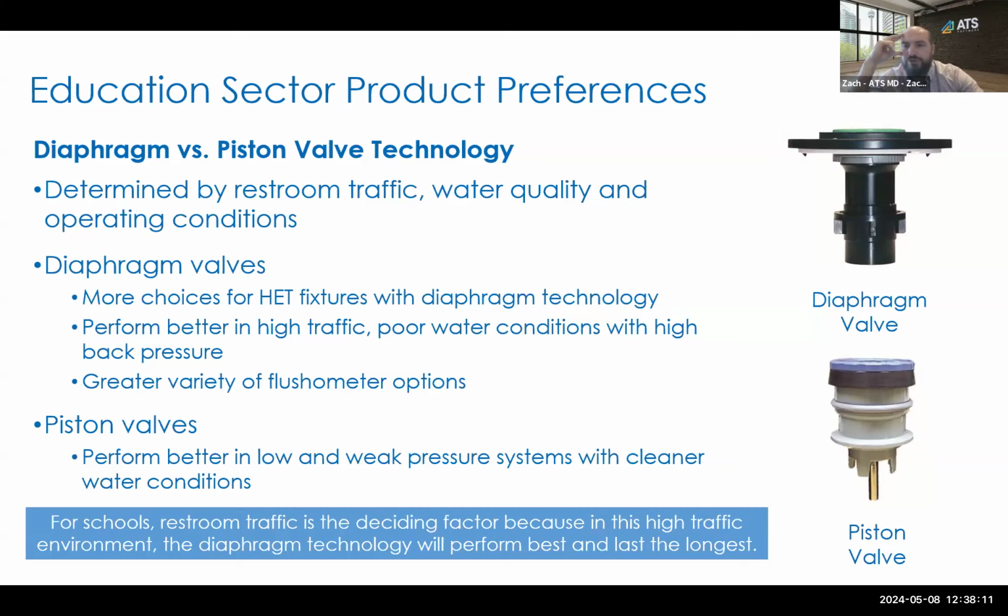Well, and the other issue that you highlight there on clean water conditions, sediment on the actual trigger activation at the bottom has potential, depending on the manufacturer. Some manufacturers have like a cleaning wiper to clean after every activation, but sediment can certainly get in there and affect it. One thing I wanted to just build an understanding of is in terms of actual numbers.